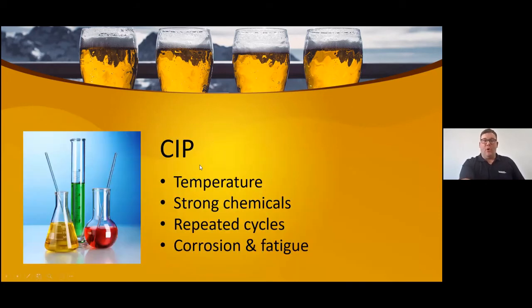Again, coming back to CIP, which is important for hygienic pumps. Can it stand up to the temperature? They can be quite hot, often up to 85 plus degrees. Strong chemicals can be used, so it's important that the elastomers selected can stand up to that. The repeated cycle, so repeatability: is it every day, every 12 hours? And corrosion and fatigue: is the pump capable of standing up to the chemicals and the repeated cycles? Some industrial pumps aren't designed for the temperature and the strong chemicals, such as caustic soda, which is often used in CIP. Sometimes the elastomers in industrial pumps aren't appropriate for that. But again, it depends what's been specified.